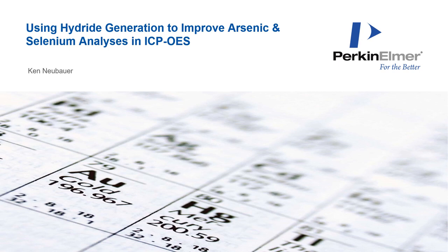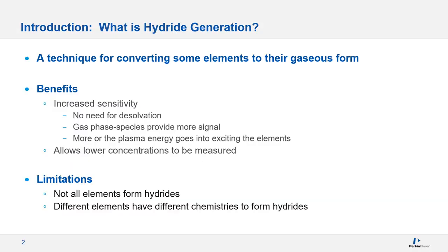Today I'll be talking about how we use hydride generation to improve arsenic and selenium analyses in ICP OES. Hydride generation is a technique for converting some elements into a gaseous form. The main benefit is increased sensitivity — there's no need for desolvation. With conventional aqueous nebulization, the plasma energy must first desolvate the droplets; with hydride generation, the gaseous element goes directly into the plasma, so all the plasma energy goes into exciting the elements, allowing us to measure lower concentrations.